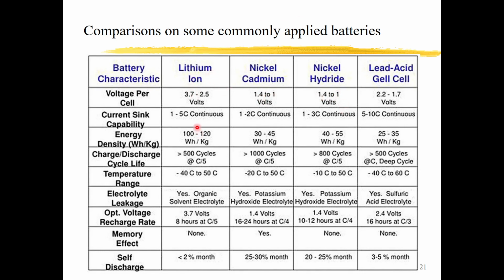For the lithium ion, of course, there are many kinds of lithium ion batteries, so the current sink capability varies a lot. Here it says 1 to 5 C continuous. We are talking about continuous, and that means in a very short time, maybe you can use a higher current. And for the nickel cadmium, nickel hydride, it may be 1 to 2, 1 to 3 C. And for the lead acid, it can afford higher current.